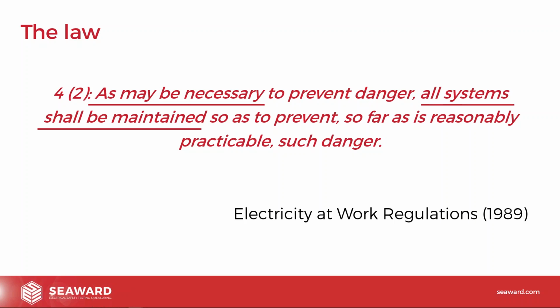So generally, PAT testing, we don't cover the fixed installation, the fixed wiring, but we may well cover equipment connected to the fixed installation, whether that's via a plug and socket or whether that's actually hardwired in. So something like a cooker hardwired in, for example, would generally, if it's in a place of work, fall under the Electricity at Work Regulations and fall under what we normally call PAT testing nowadays. It'd be fixed equipment testing. So it's important to understand this idea of all systems does actually apply to everything. It's not just the fact that it's portable stuff and things like that. So all electrical equipment used in the workplace, whether that's battery powered equipment all the way up to fixed equipment, and even the Electricity at Work Regs, it's all the fixed installation.